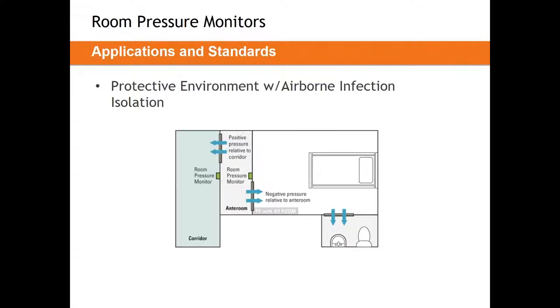The third type is the combination: protective environment with airborne infectious isolation. These patients are immunocompromised but also have a disease that could spread to the rest of the building. They need to be separated for the building's sake and for their own sake. These spaces have more physical separation from the rest of the building, meaning they have an anteroom. You need two room pressure monitors — one measuring from corridor to anteroom and one from anteroom to isolation room. Sensors go right above each doorway, with monitors at each door clearly visible.